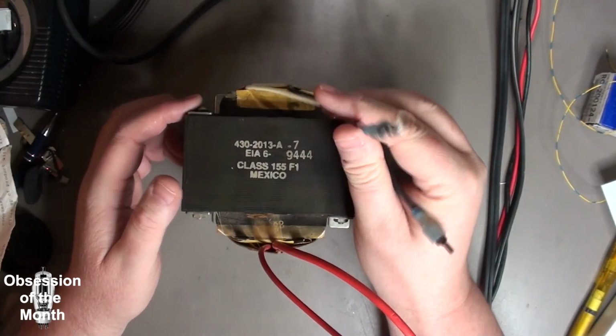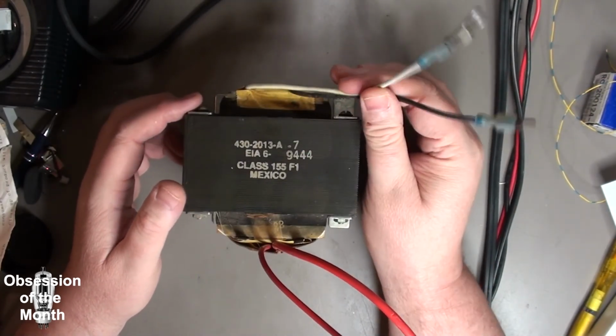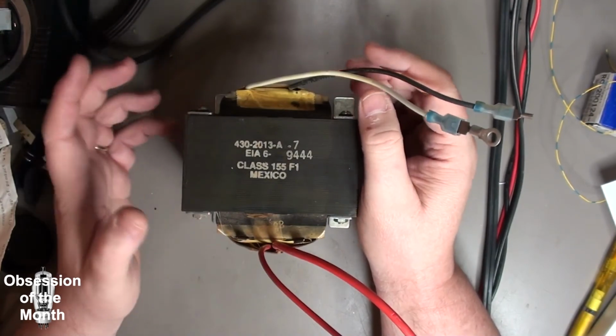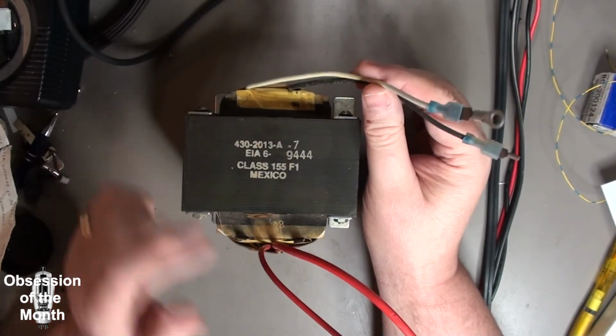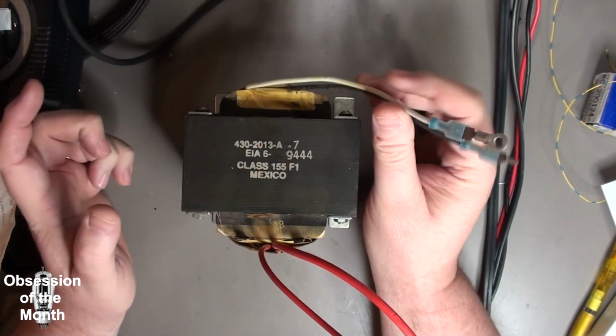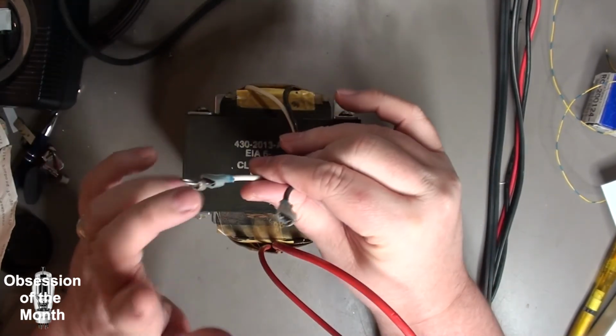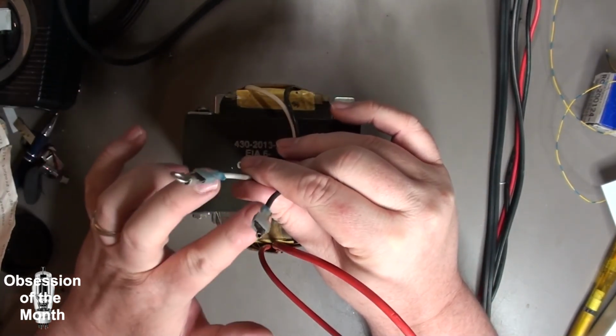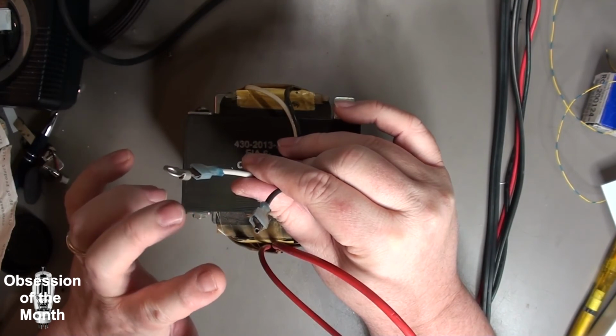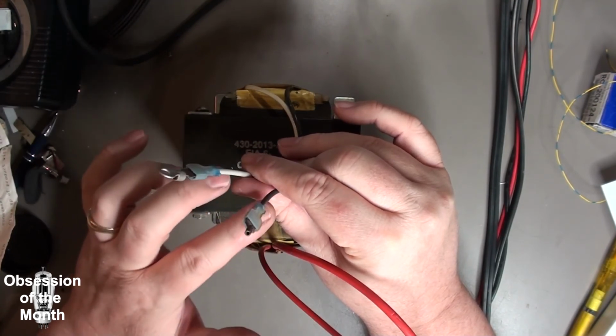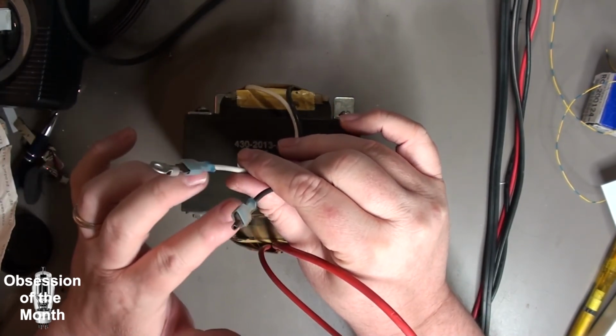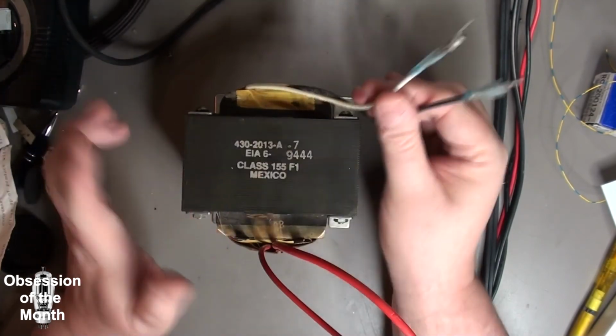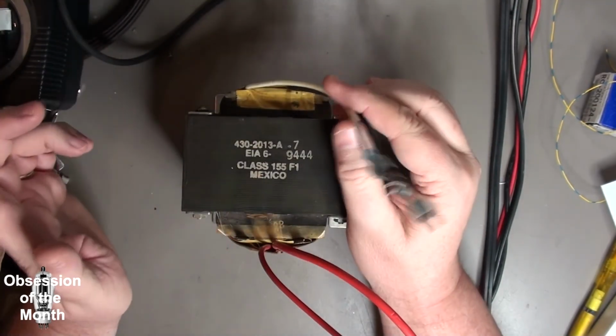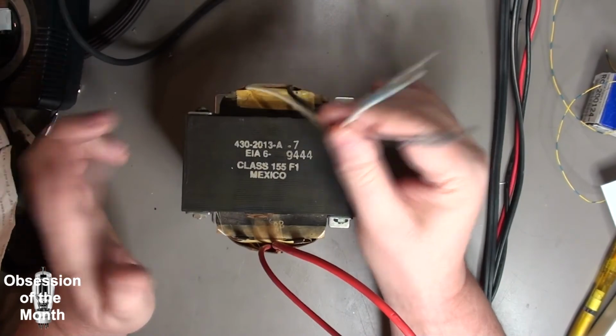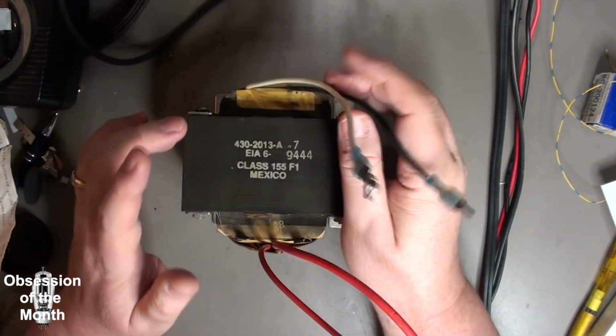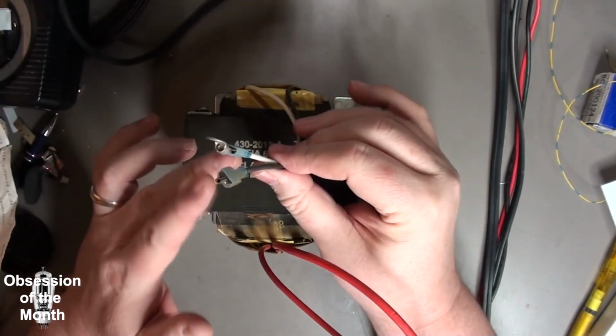So you put 120 volts in, ideally on a variac, and measure the output voltage. You should see hardly any amp draw on that side. If you start putting voltage on it and get a high amp draw, there's either a short or you're hooked up to the wrong wires.